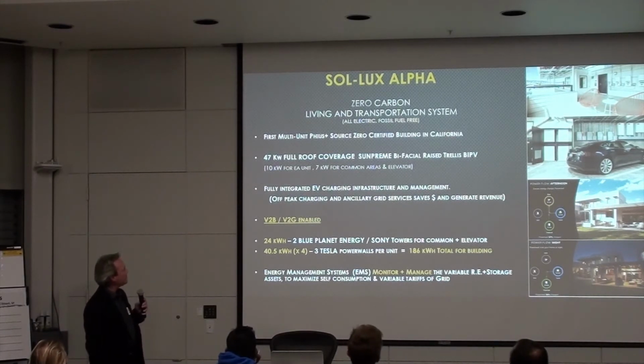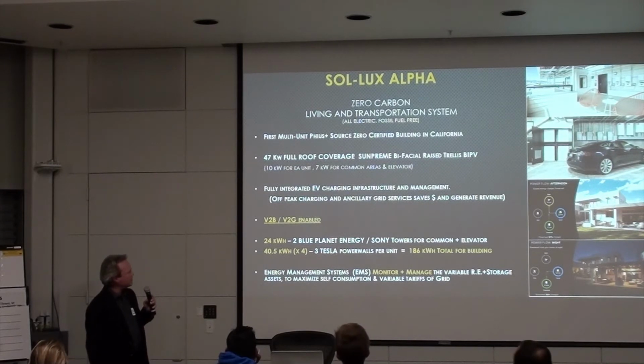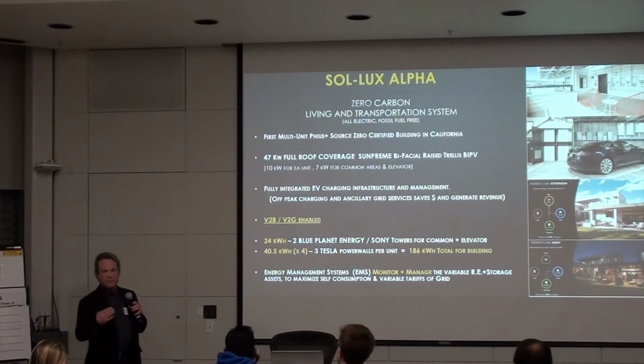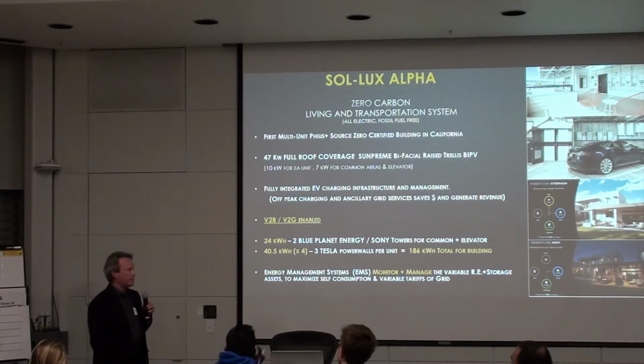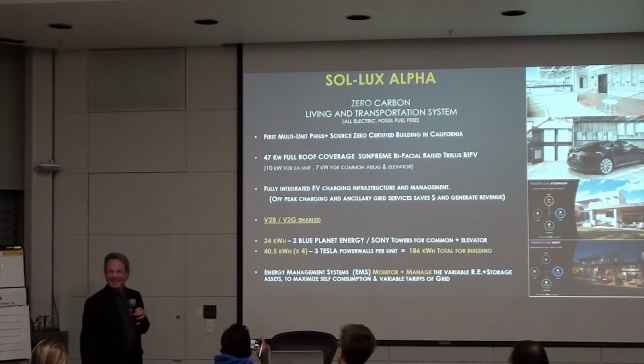It has about 47 kilowatts of full roof coverage, Sunpreme bifacial trellis, about 10 kilowatts per unit, and 7 kilowatts for the common areas. Even though it looks like one big array, it's actually separated into 5 separate systems. Originally we planned it as one big battery for the building with everybody sharing energy, but that was against interconnection laws, so we had to separate it out and re-engineer it. We did a lot of re-engineering on this building.